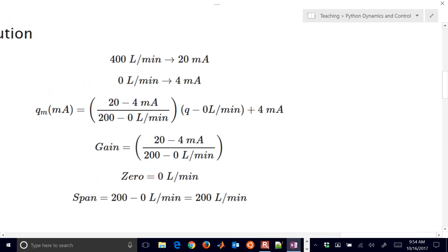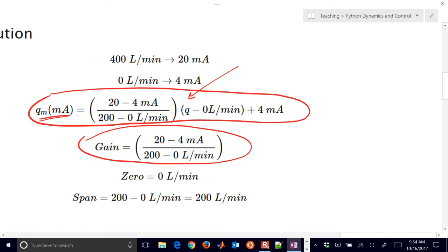So there's our solutions right there. Just to review, you have the equation that defines the, this is a milliamp signal for a given flow rate input. So you can plug in any flow rate right there and then calculate a milliamp signal. Even though there's just an equation of a line with our gain, our zero, and our span.